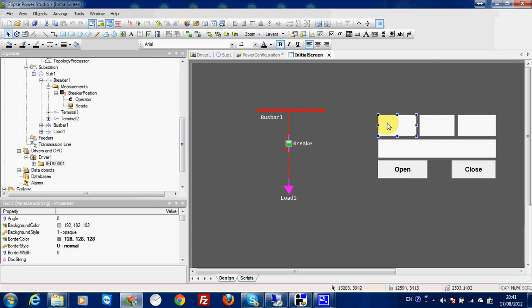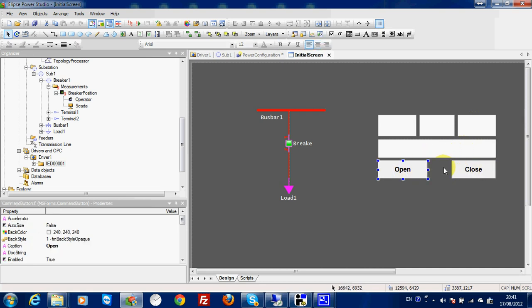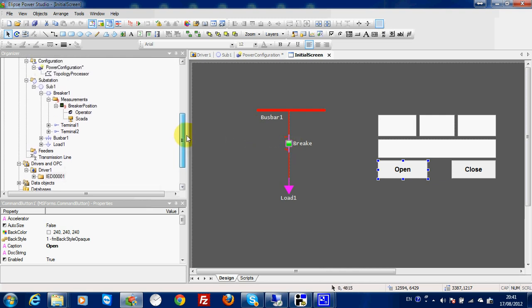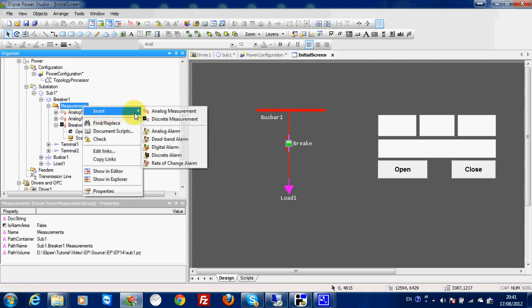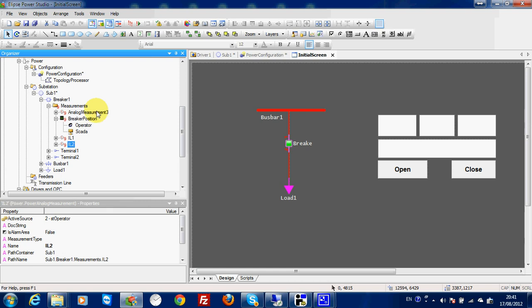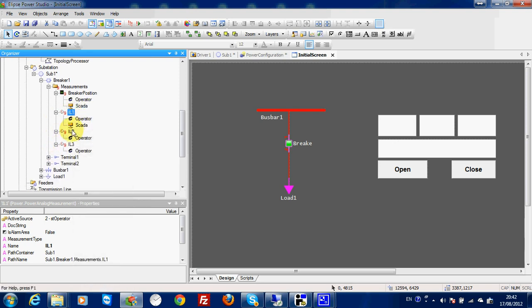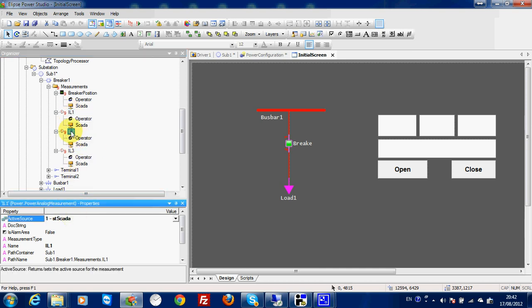Here you will see the value of the three phase currents, breaker position, and here I can send a command by E3 scripting. Now I just want to do the same thing here in my breaker. So the first thing to do in measurement is I can insert the analog measurement to show we can do the exact same thing. Here I can write IL1, IL2, IL3, and I can insert SCADA for each. The active source will be SCADA for the three.